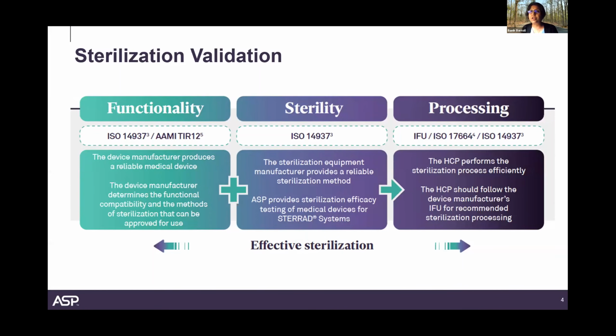Sterilizer manufacturers talk of sterility. And when we talk of sterility, it is around the ISO 14937. And who talks about the functionality? Because I sterilized a device, but I'm not aware whether it's functional or not, because I didn't check their IFU. It might not give the required outcome to the surgeon because he would use the device. So the device manufacturer talks about the functionality. The sterilizer manufacturer will give you the sterilization efficacy, a SAL of 10 to the power minus 6. When you add both together, you get an outcome which is called the process outcome, the sterilization outcome.